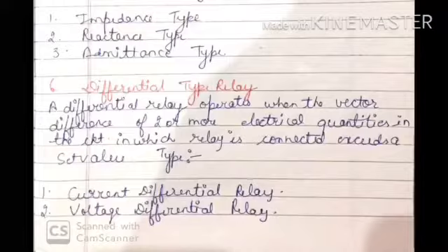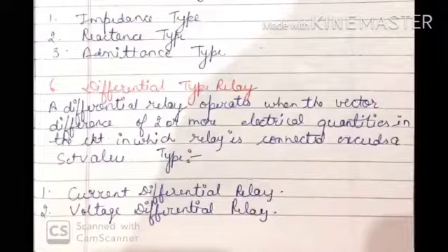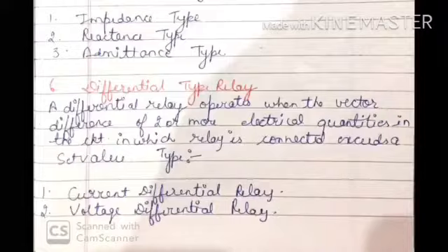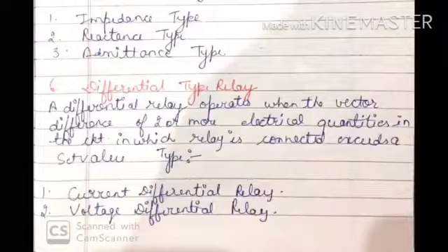Then we have the differential type relay. This relay operates when the vector difference of two or more electrical quantities in the circuit exceeds a specified value. There are two subtypes: current differential type and voltage differential type. In the current differential type, the relay compares the current entering a section of the system and the current leaving the section. Under fault conditions, these currents are different, and the relay operates.